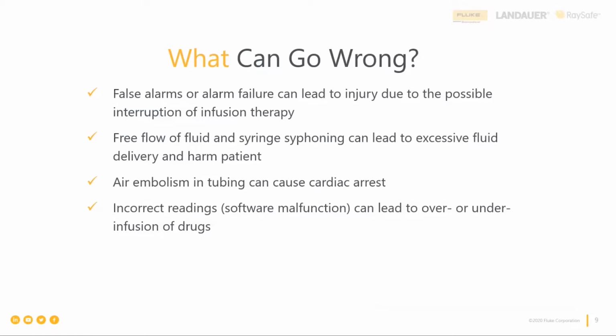Sure. I'll be happy to elaborate a little bit. We all know that there can be false alarms in all kinds of medical devices, but especially in infusion pumps. Some of the false alarms you can get have to do with air bubbles and obstruction of the fluid line. The important thing in the large volume continuous flow pump mechanisms is that our goal is a controlled flow of the infusate, the liquid, the drug or whatever it is that's being delivered to the patient. Sometimes, however, we need a free flow in an emergency situation. So that really is an important feature of the infusion pump that needs to be dealt with and made sure that it's working properly.